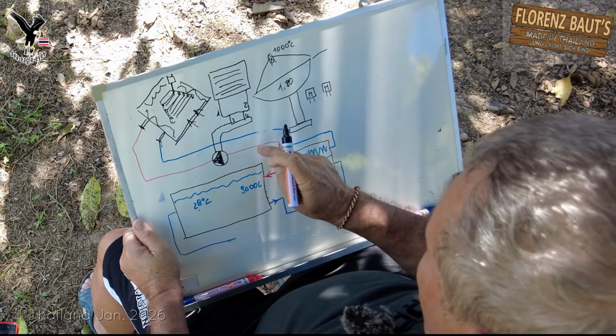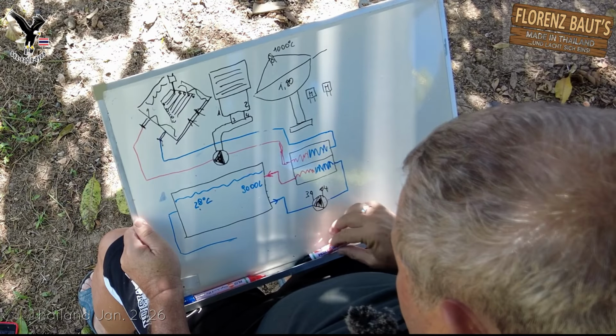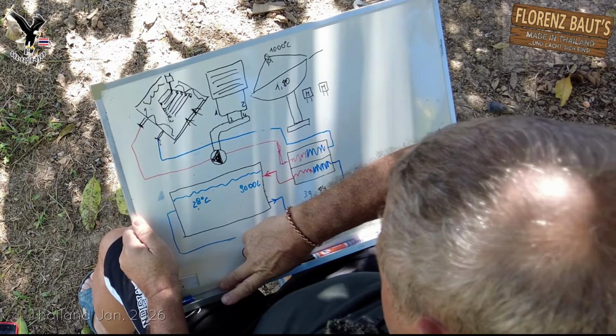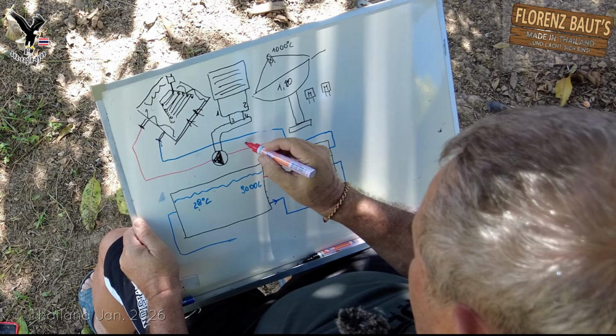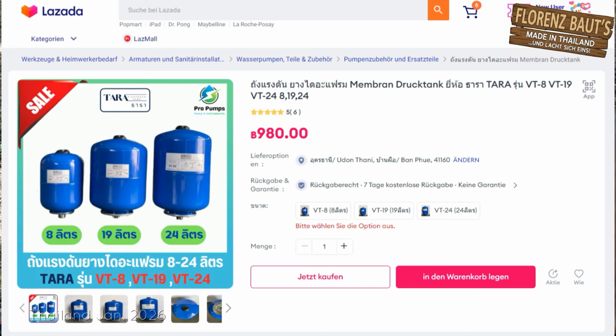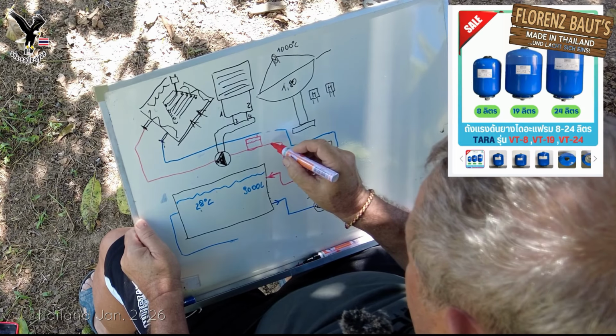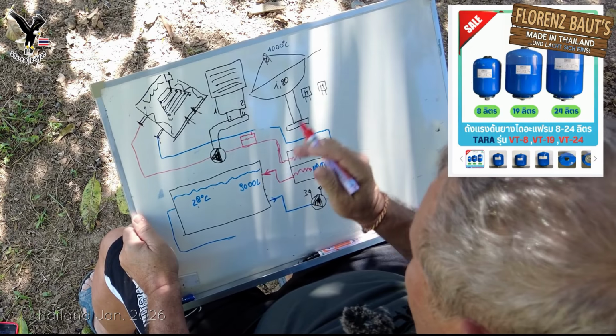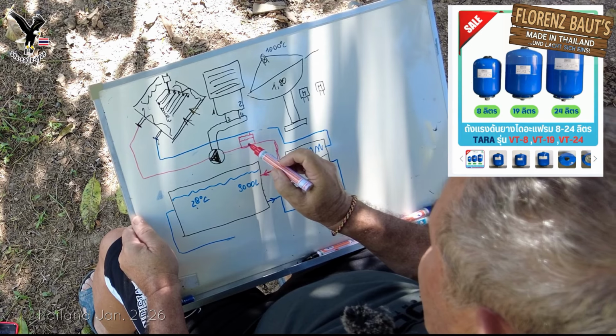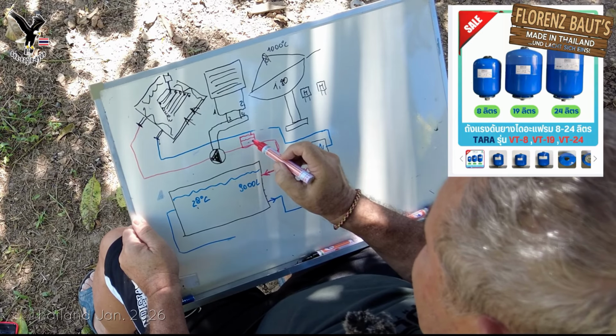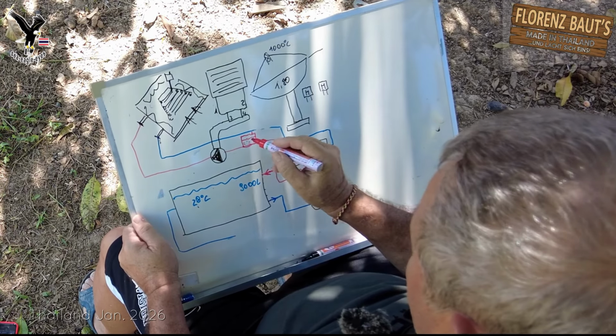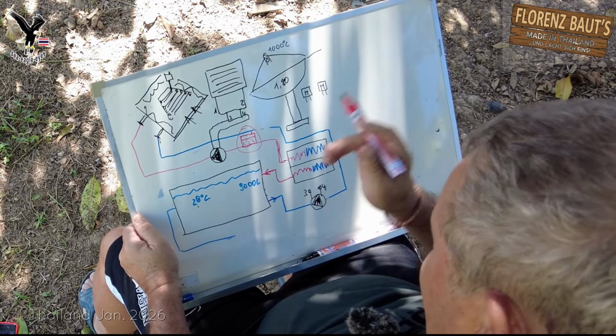So here in the system, in front of the pump, there must be an expansion tank here to equalize the pressure. There's nothing but a membrane inside, a connection, a pressure relief valve, so that when the water in the line expands as it gets warm, then here in the expansion tank, the pressure is stabilized. And also if there are fluctuations, that's what this is for. So there's also water in it. And a safety valve. Normally you can buy this as a complete unit.